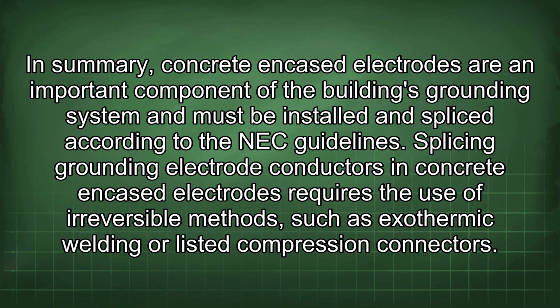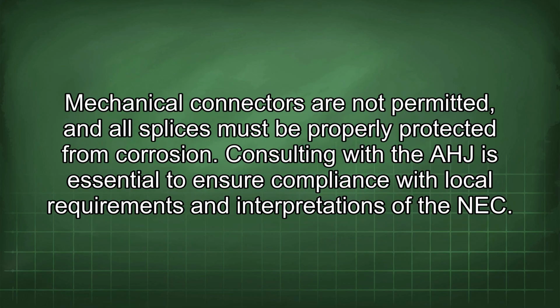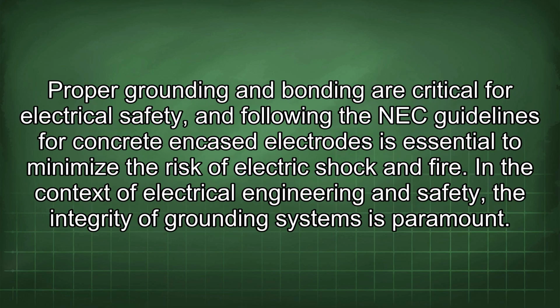In summary, concrete encased electrodes are an important component of the building's grounding system and must be installed and spliced according to the NEC guidelines. Splicing grounding electrode conductors in concrete encased electrodes requires the use of irreversible methods such as exothermic welding or listed compression connectors. Mechanical connectors are not permitted, and all splices must be properly protected from corrosion. Consulting with the AHJ is essential to ensure compliance with local requirements and interpretations of the NEC. Proper grounding and bonding are critical for electrical safety, and following the NEC guidelines for concrete encased electrodes is essential to minimize the risk of electric shock and fire.